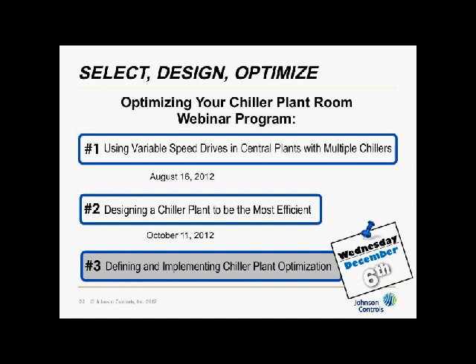I'm scrolling down. Can we run the chiller at full load for a long period of time when we have another standby chiller available? Some people say it's not good to run at full load for a long period of time. I don't know of any reason why you can't run at full load or even above that for a long period of time. The main thing to be concerned about is not so much whether you're at full load, but are you at your high head. If your head gets too high and you start doing CPO algorithms that lower flow in the condenser, then you could literally put your chiller in surge. There's more consideration for that, but running at full load, it really shouldn't hurt your chiller if you ran that way forever.